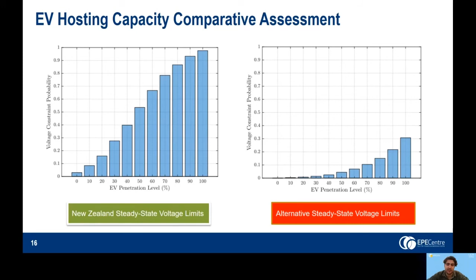The table shown here provides a comparison of the hosting capacities assessed using both the New Zealand voltage limits and the proposed alternative. When using the New Zealand voltage limits, EV hosting capacities are generally conservative. The only way of increasing the EV hosting capacity is by selecting a higher percentile value. However, in doing so, the probability of a constraint occurring at the assigned hosting capacity is increased. By adopting the alternative limits, EV hosting capacity can be increased without compromising on confidence.